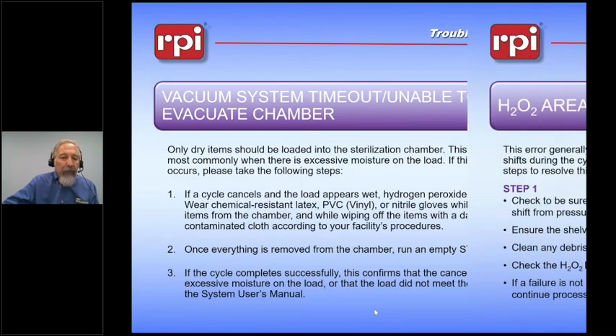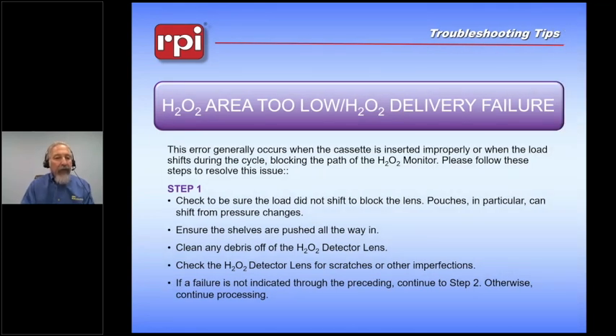Also, one of the things that the machine looks at as an error is if the hydrogen peroxide made it through the system. And there are several places where the hydrogen peroxide might not reach the detectors. One of the most important problems is with the hydrogen peroxide detector itself. Since it's located in the front of the chamber and the load is directly below it, if the load put into the chamber was not far enough into the back of the chamber or has shifted during the process of closing the door, it's possible that some of that material might get in the way of the hydrogen peroxide detection system. So we want to be sure that there is nothing blocking the light between the UV bulb and the detector at the bottom. Pouches are notoriously bad for this.